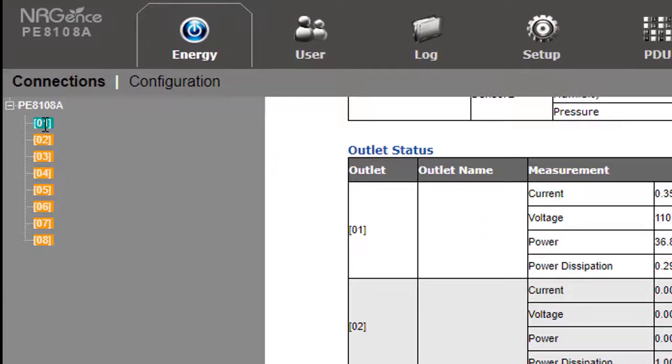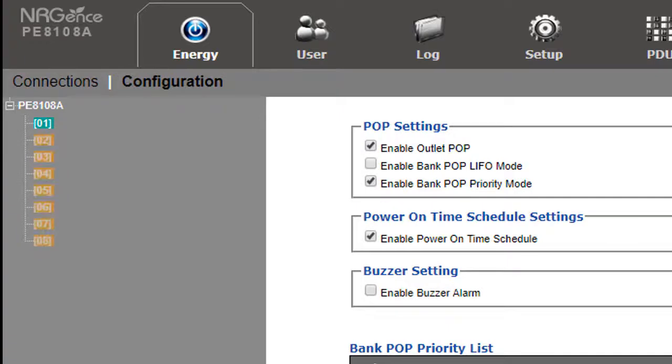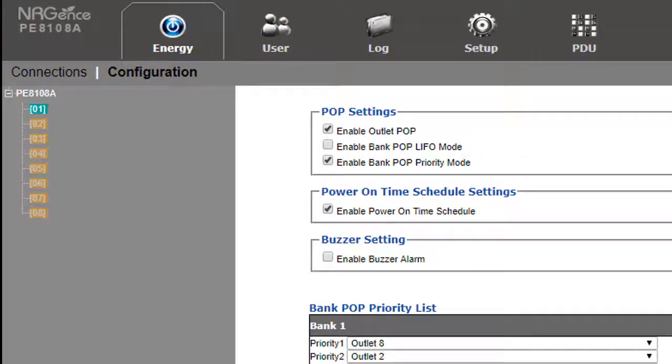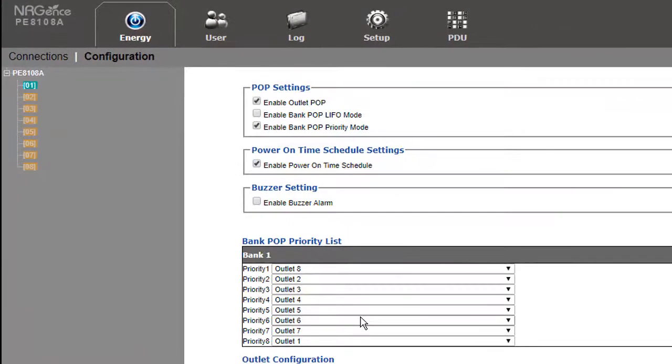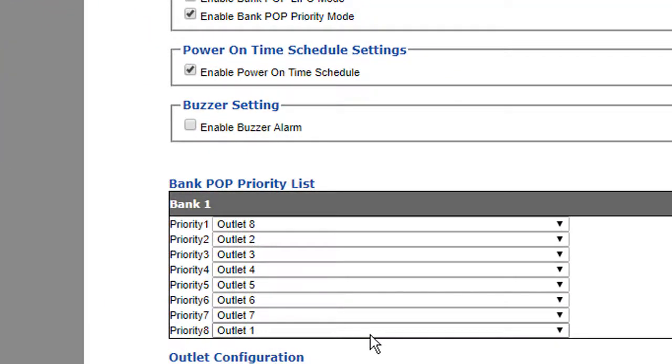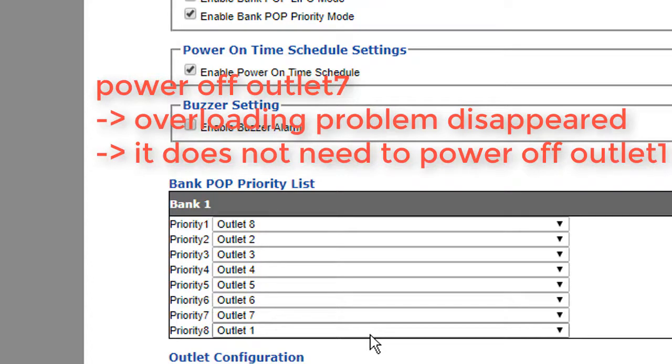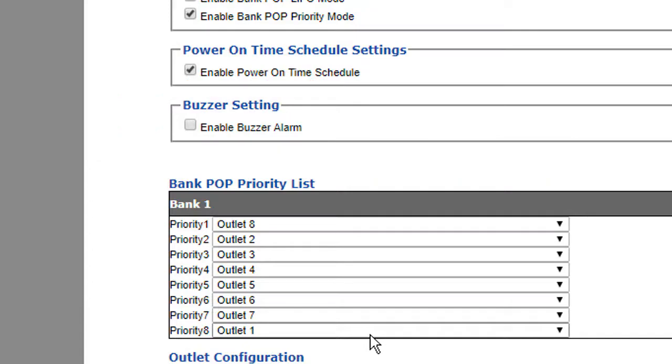Why does outlet 1 still light green? Because when the system powers off the outlets one by one, after powering off outlet 7, which caused the overloading problem, the total power consumption will be lower than the max threshold. The PDU system does not need to power off the last port, outlet 1, so we can keep the outlet 1 server PC working.